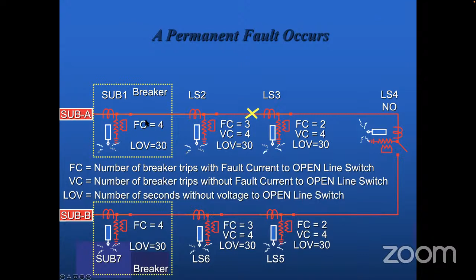Then you have a fault here. That means this substation is feeding the fault, and a trip is going to happen. Remember, this is a breaker; these others are normal switches. So you are opening the breaker here. Now when you open the breaker, what happened? Number of breaker trips with fault current to open the line switch. This is the first time the breaker opened and this agent saw the fault current. Because this is a radial system, this other agent has not seen the fault current, because the fault is here. But when this line opened, it did see VC1, the number of breaker trips without fault current. Its setting is VC equal to 4.